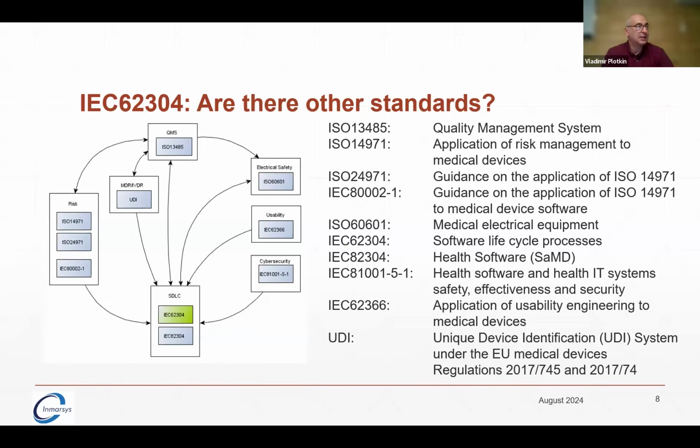So these are the standards that 62304 is interfacing with. As you can see, there are quite a few. You can divide them into several groups. The big one is the QMS, Quality Management System, ISO 13485, and that is the main standard any medical company operates in. If you're not certified to 13485, you cannot sell a medical device or medical software, because you may be developing your software as a medical device rather than a physical device, something we can actually hold.